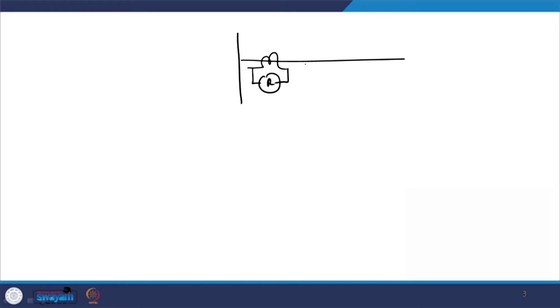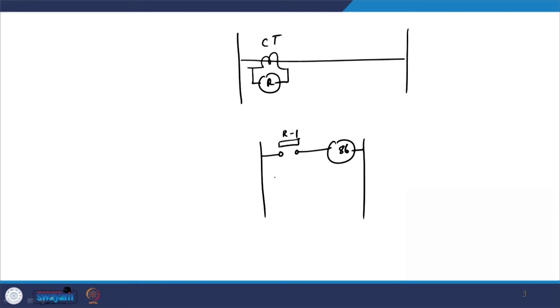Let us say this is an overcurrent relay, this is the CT, and on the control circuit part the relay has the contact, let us say R1. This contact is given to the auxiliary coil of the auxiliary relay, and then you have the contact of the auxiliary relay, 86(1), which is given to the 52 TC, that is the trip coil of the circuit breaker.